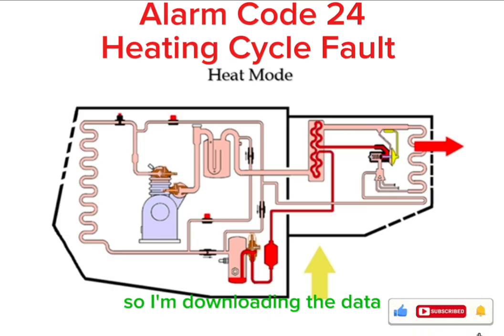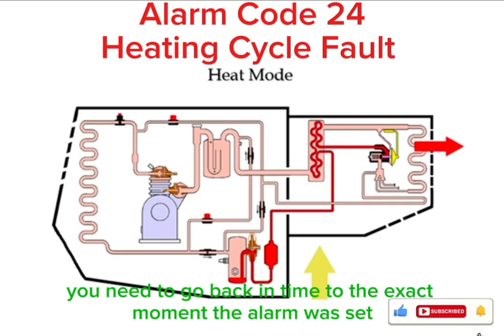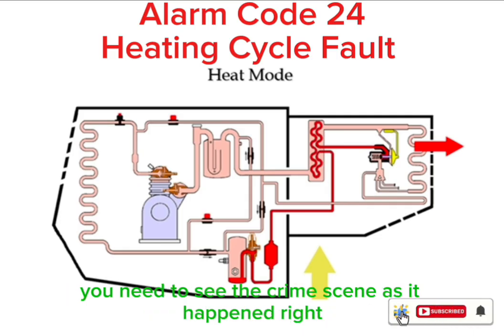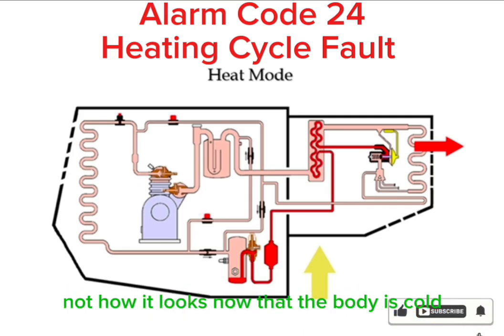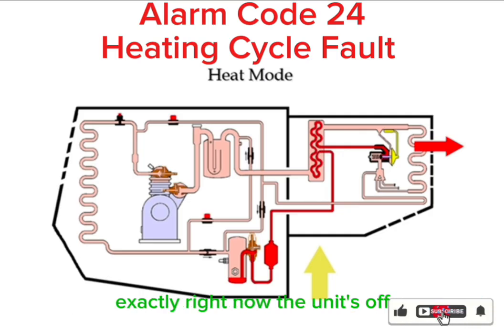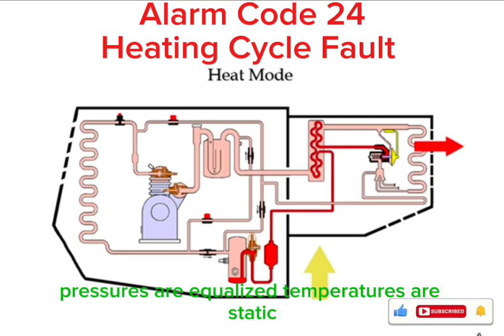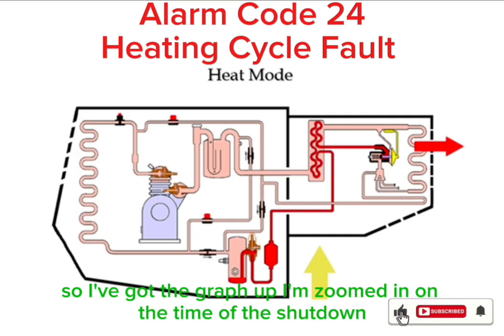Okay, so I'm downloading the data. I'm looking at the technician user level, I assume. That's where the gold is. And here's the secret sauce. Do not just look at the last 5 minutes. You need to go back in time to the exact moment the alarm was set. You need to see the crime scene as it happened. Right, not how it looks now that the body is cold. Exactly. Right now, the unit's off. Pressures are equalized. Temperatures are static. It tells you nothing.